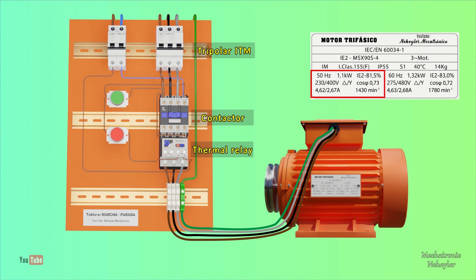While the current value supported by the other elements can be higher and there would be no problems. Take into account that the current value of the power cables must withstand more current than the three-pole thermomagnetic switch. For this motor, we can work with a cable with a minimum section of 2.5 square millimeters and an ITM of 16 amps.